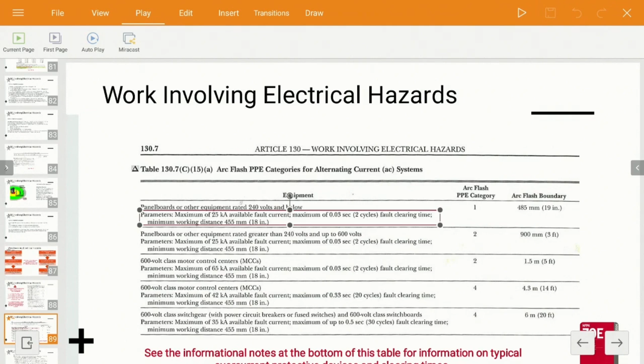Okay? And the notes underneath that table give you some examples here. The thing I have a problem with, number one, is I don't think anybody's going to read this in the field. They want to get the job done. The second problem I have with this is, see where it says 1.5 cycle of fault clearing times typical for molded case circuit breakers rated less than 1,000 volts, blah, blah, blah. What does typical mean? Does it mean always? That's the problem I have. I don't like taking a chance when it comes to electrical hazards.